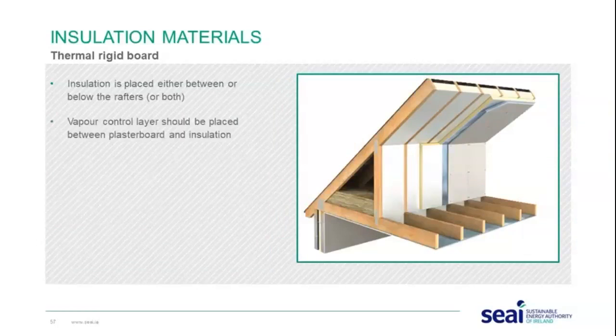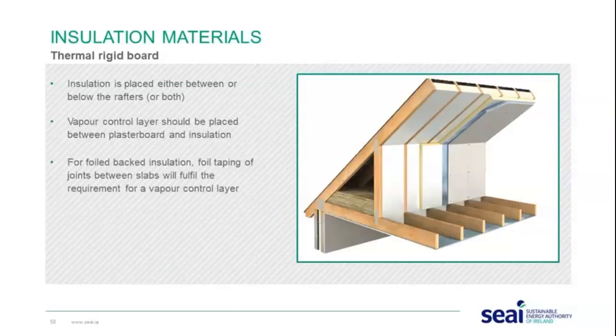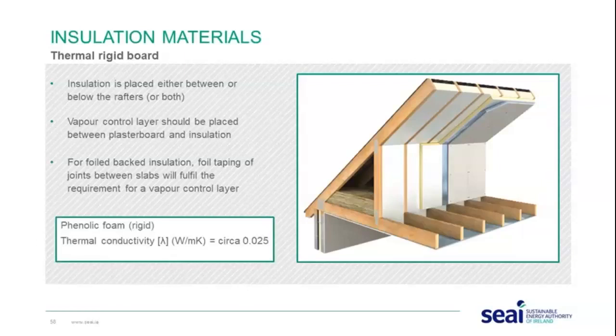For thermal rigid board, insulation is placed either between or below the rafters, or both. A vapour control layer should be placed between the plasterboard and the insulation. For foil-backed insulation, foil taping of the joints between the slabs fulfils the vapour control layer requirement. The thermal conductivity is around 0.020–0.025, though this varies depending on the actual material used.